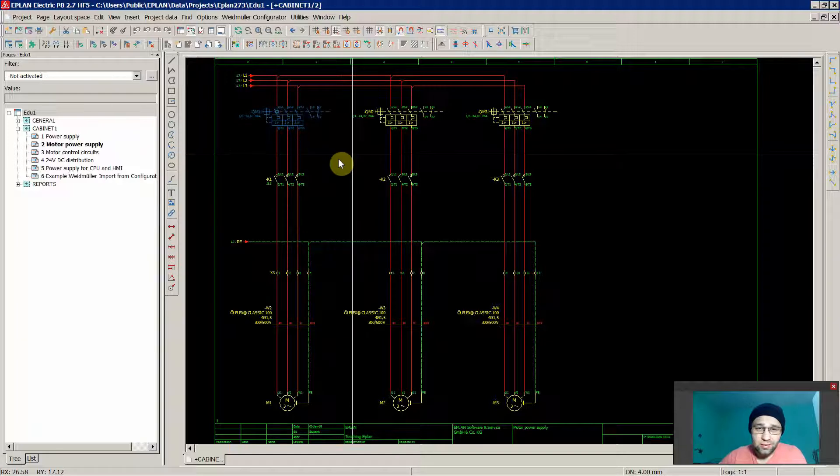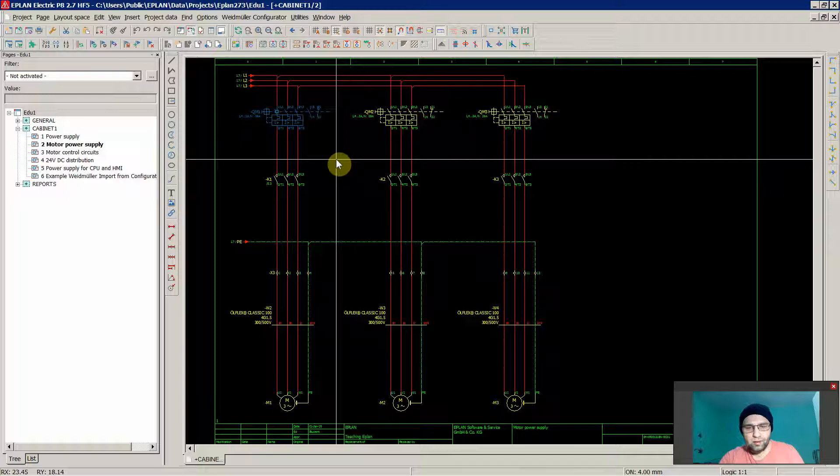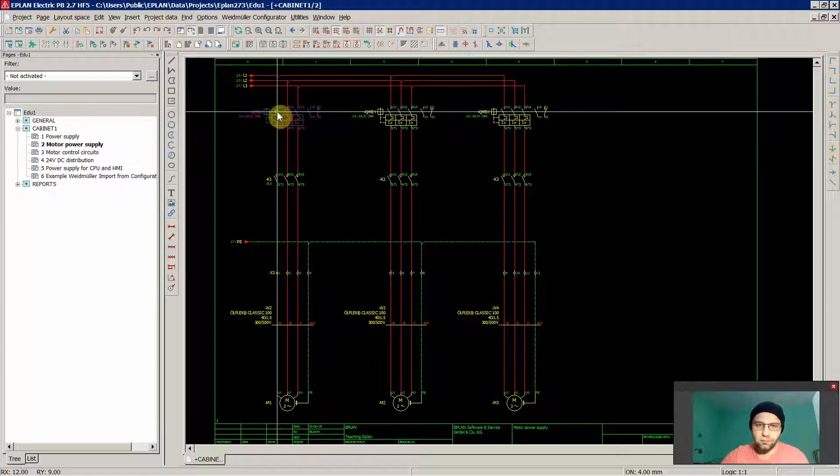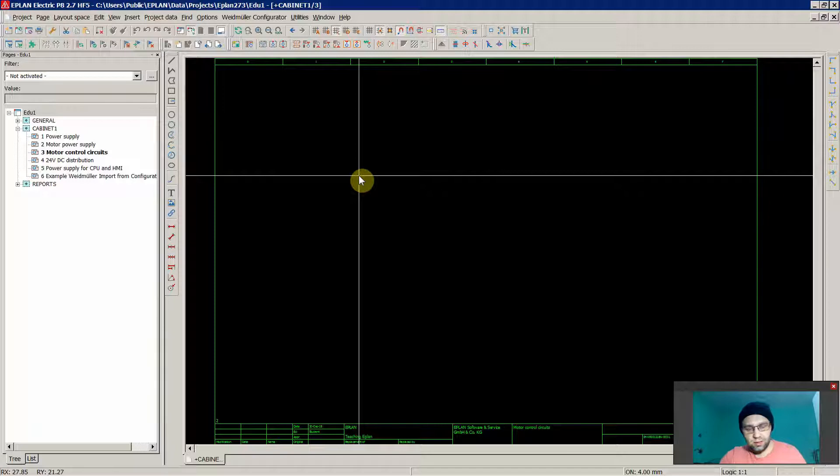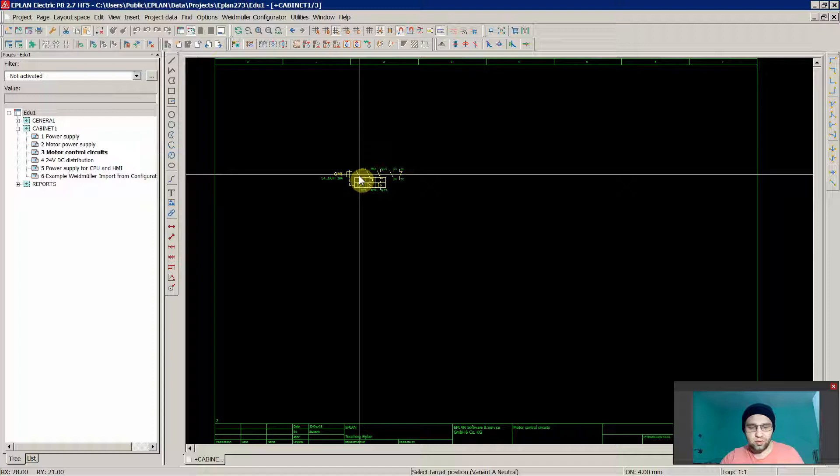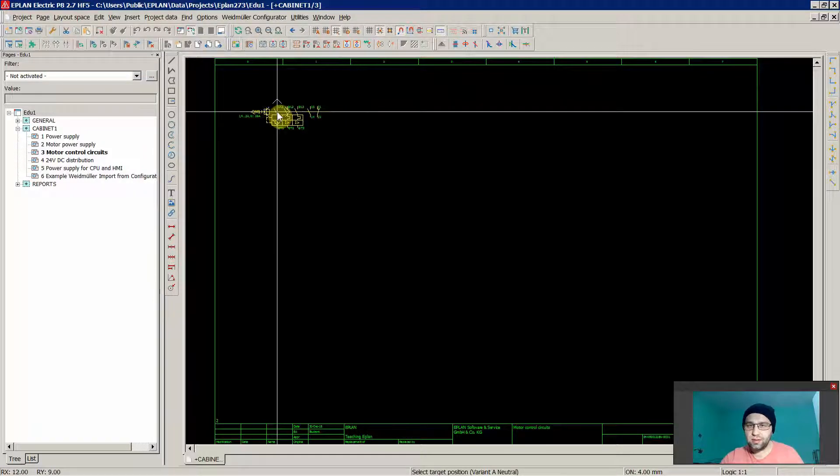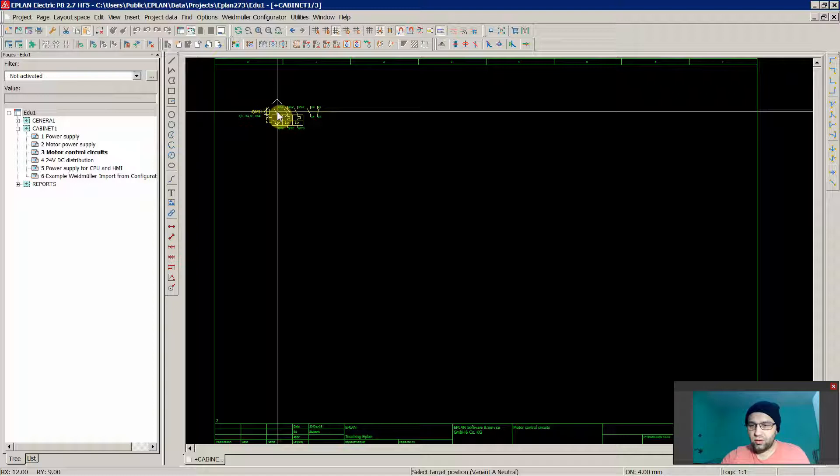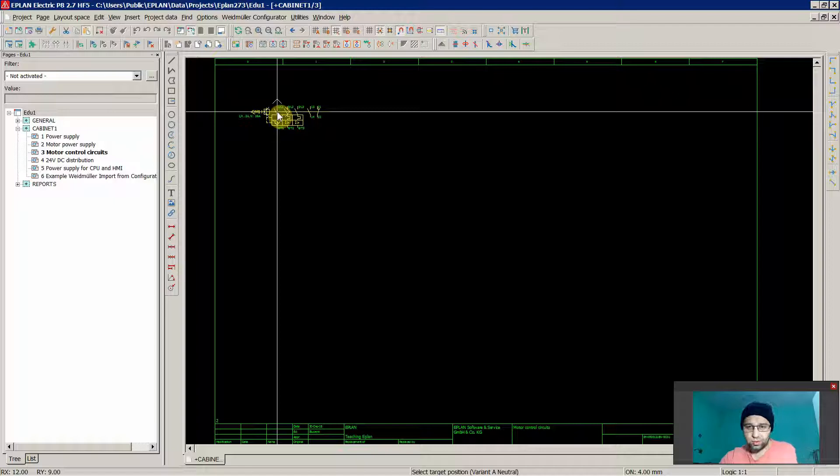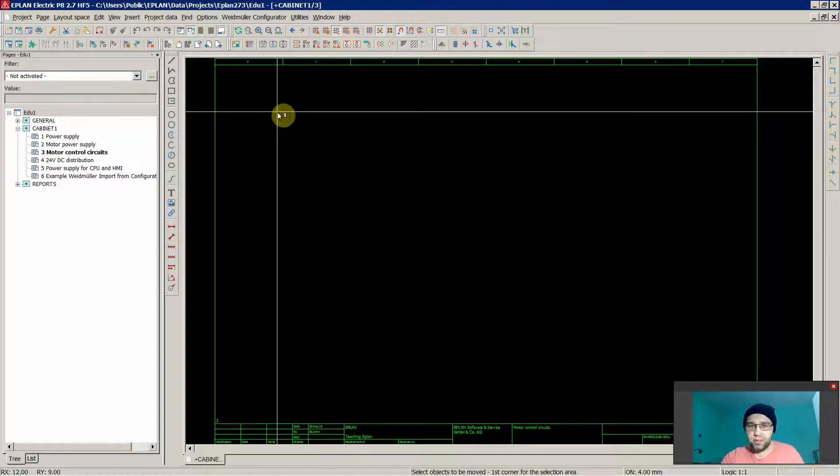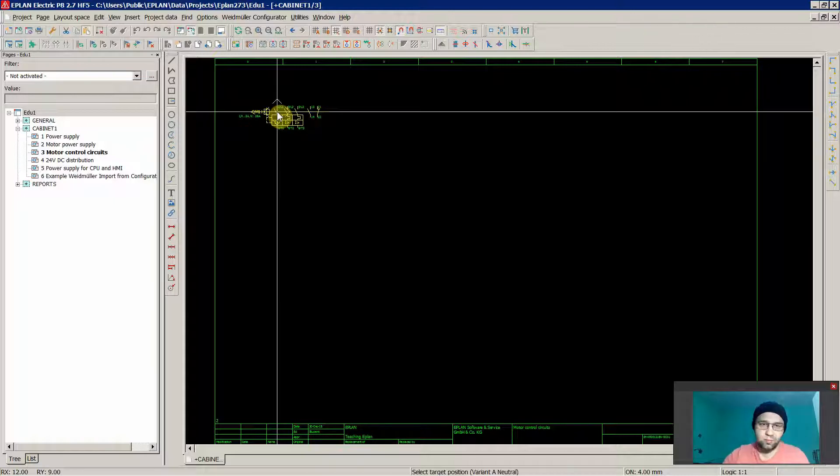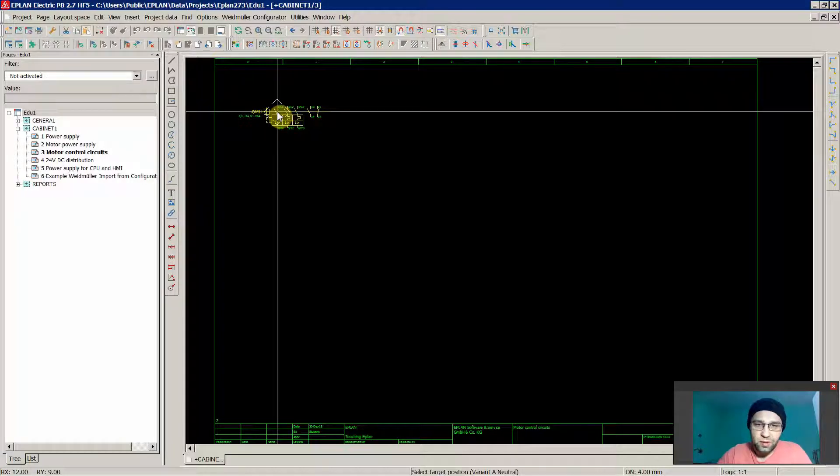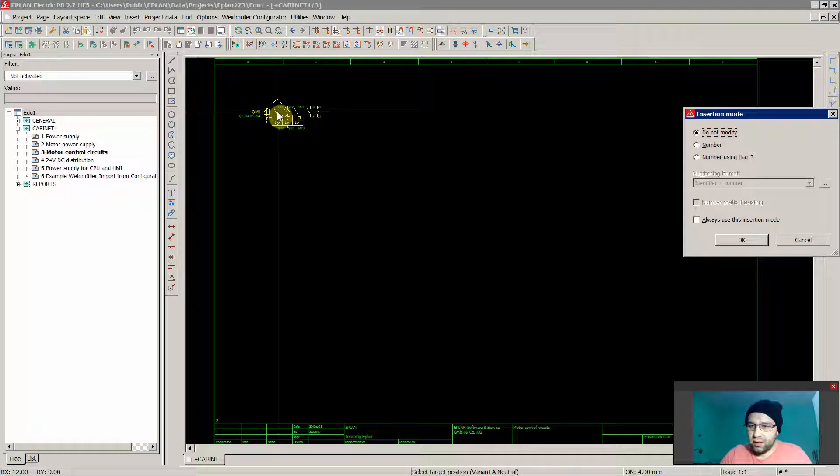For example, if you would like to copy this element, motor overload switch, to another page, you would say Control C and Page Down, you would say Control V like in Windows. Some of the shortcuts are working like in Windows. Then you would press Y and X so you see the connection over here right in the top corner. Once again, Control V, Y and X, then you place your element on the exact same position as it was on the previous page and then press Enter.